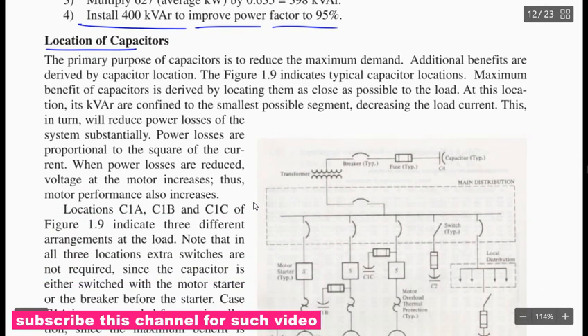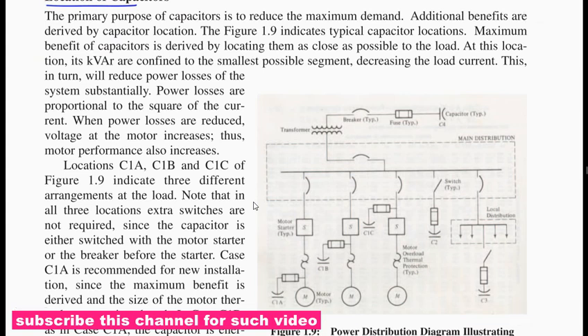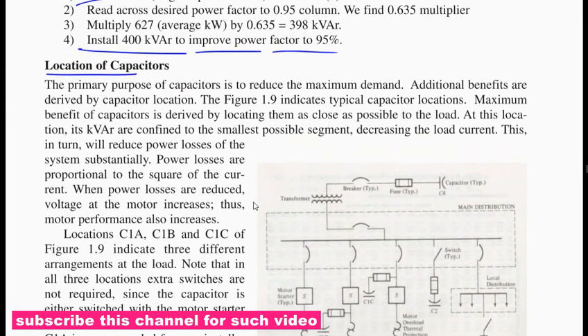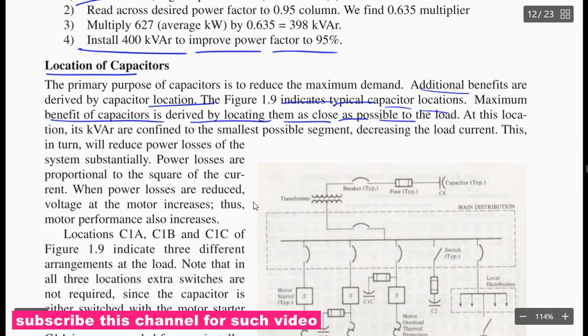Location of capacitor. The primary purpose of a capacitor is to reduce the maximum demand. Additional benefits are derived from the capacitor location, and the figure indicates typical capacitor locations. Maximum benefit of a capacitor is derived by locating it as close as possible to the load. At this location, its kVAr are confined to the smallest possible segment, decreasing the load current. This will reduce the power losses of the system. Power losses are proportional to the square of the current, so power losses are reduced. Voltage at the motor increases, and thus motor performance also increases.